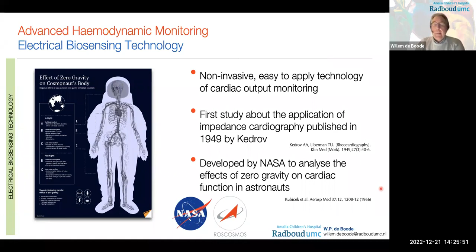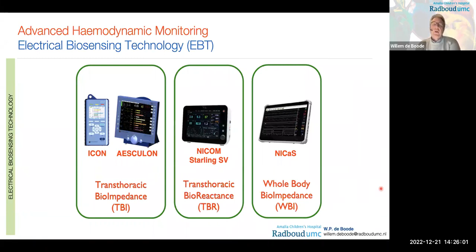In this technology, we have the transthoracic bioimpedance, the ICON or the Aesculon, the transthoracic bioreactance, the NICOM, or nowadays the Starling SV, or the whole body bioimpedance, the NICaS. In this technology, you use the fact that electrical conductivity of blood is higher than that of fat, muscle, and air. If you apply a high frequency, very low magnitude current across the chest via electrodes, that distributes mainly to the blood. And you can calculate the bioimpedance as the ratio between the measured voltage and the applied current. And if the current is of a constant amplitude, there's a direct relation between the measured voltage and the impedance.